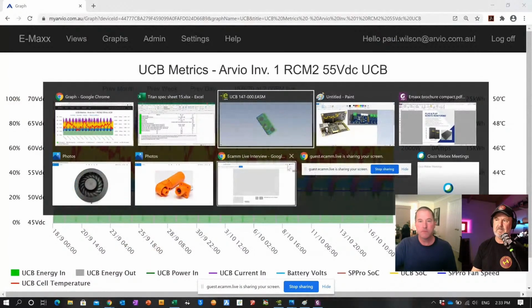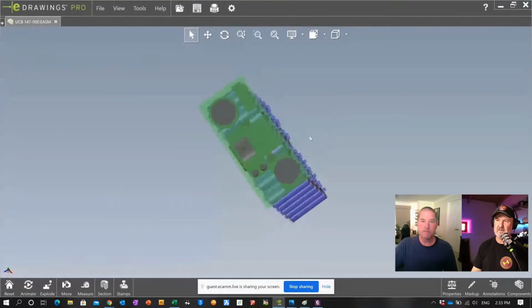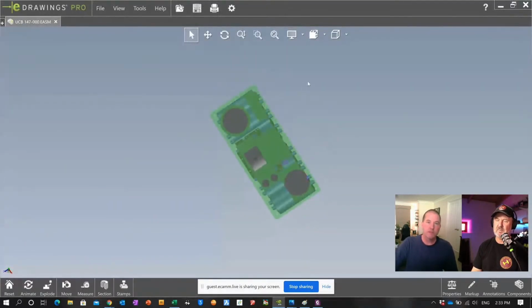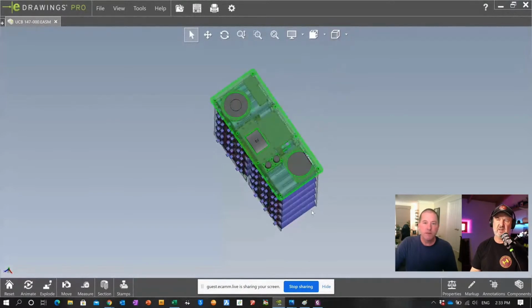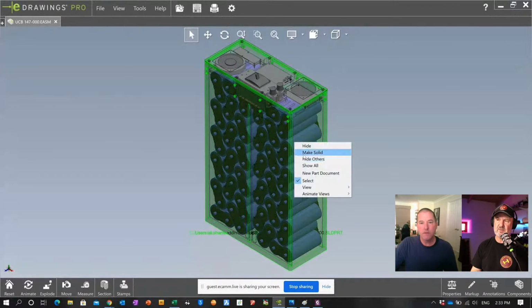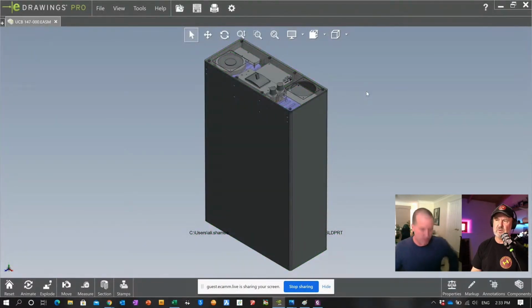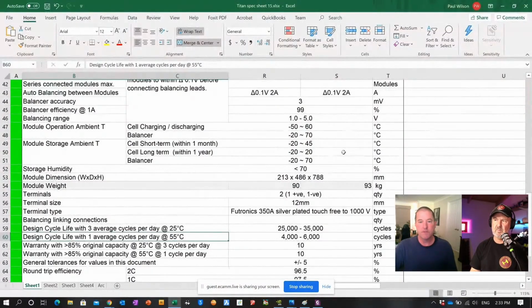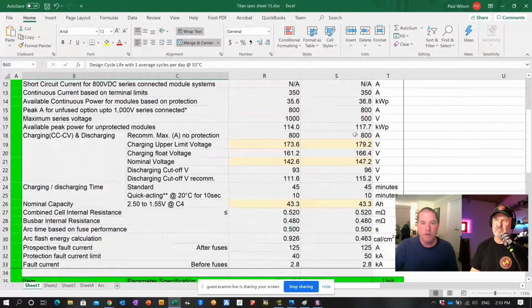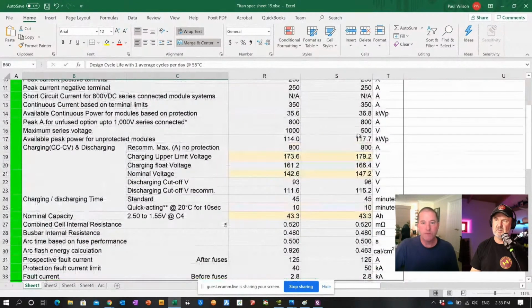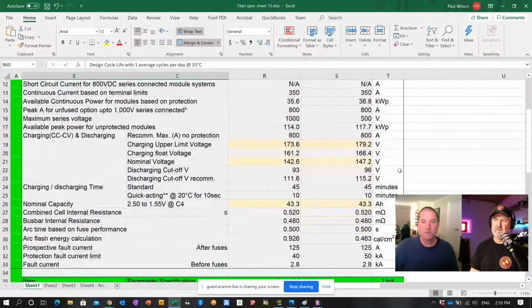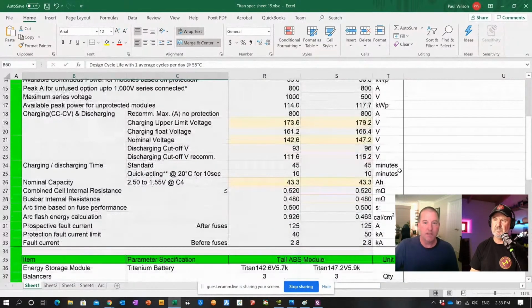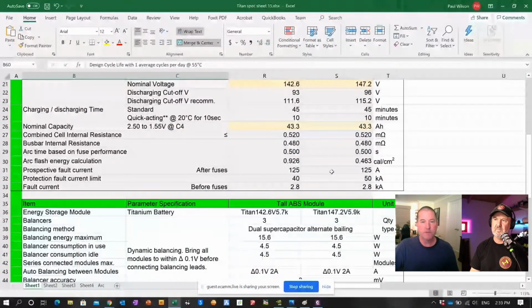Right. So let's go back to that picture. So you took the cover off the UCB and you were showing us what's inside. Yeah. Just pull it up again. Hold on. That's it. So there's 64 cells in there, and I'll just turn it here again. So this is the 140 something volt unit. Is that what you're describing? It's 147 volt nominal. Yep. So its voltage charge window is from 100 to 170. That's the tolerable window. Yep. But the nominal voltage window that we recommend you use is about 110 to 165 volts. So you couldn't overcharge it with an SP Pro because it can't go over 170. The SP Pro can't charge past 165. You can DC couple with it, we did a project recently where we DC coupled 20 kilowatts of PV to the 120 volt bus or 145 volt bus.